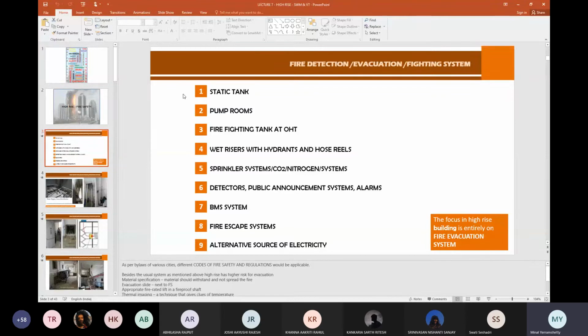You have firefighting tanks at the OHT level, but not just at the OHT level, also at all the mechanical floor levels, because your entire building cannot be fought with just one fire supply. It has to be done at a zonal level. You have to zone your building and see how you can take the water up, because the same principle applies, in fact more so here, because you are carrying water down through huge 6-inch pipes, not small ones. The pressure would be tremendous, and you have booster pumps on top of it. It's going to be terrible if there is no control taken on that, and that is the reason you zone the building and fight the fire zonal-wise.